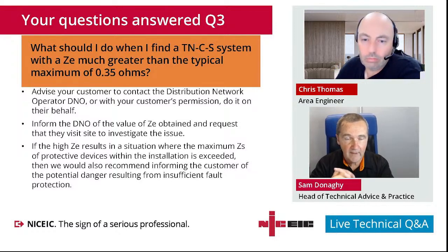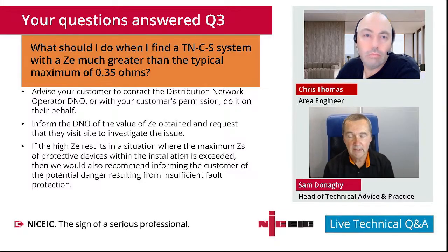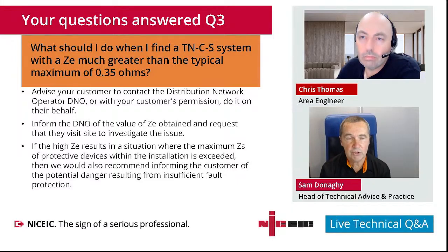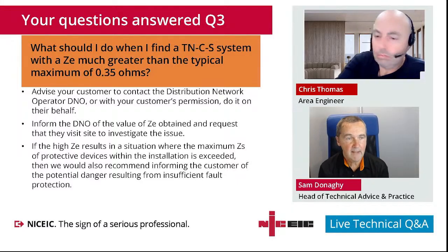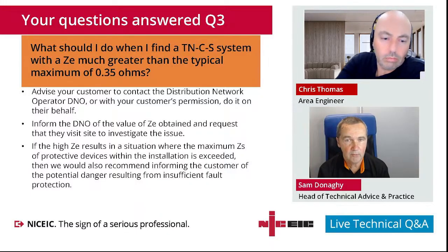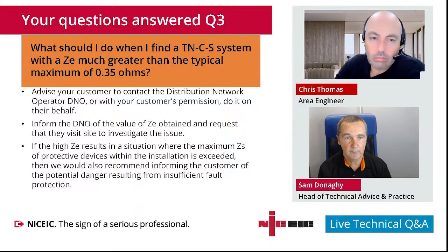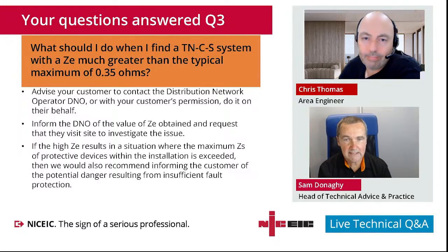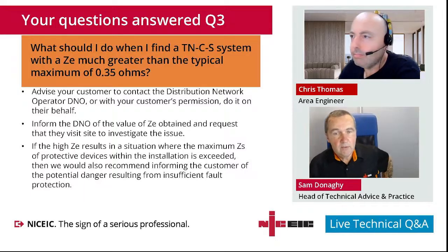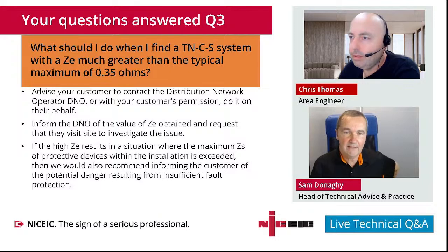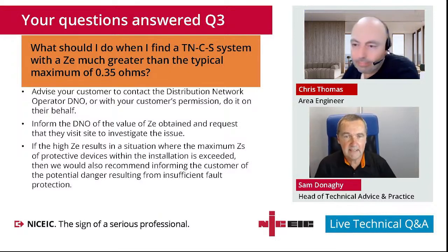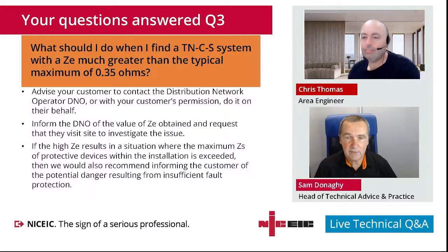Inform the DNO of the value obtained, and request that they visit site to investigate the issue. Now, they may or may not choose to do so because they may know, for example, that it's always been greater than 0.35, and they may not be concerned as long as it's stable. So one thing to think about is that the 0.35 and the 0.8 value and the 20 ohm value for TT, they're not actual maximum thresholds that the DNOs have to achieve.